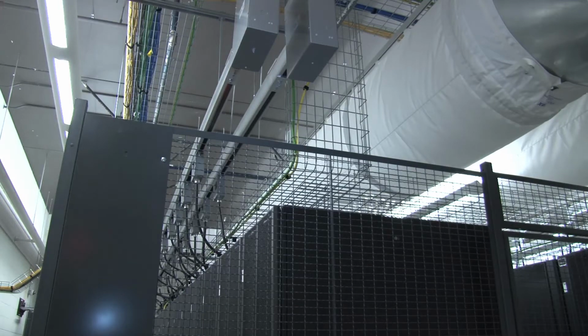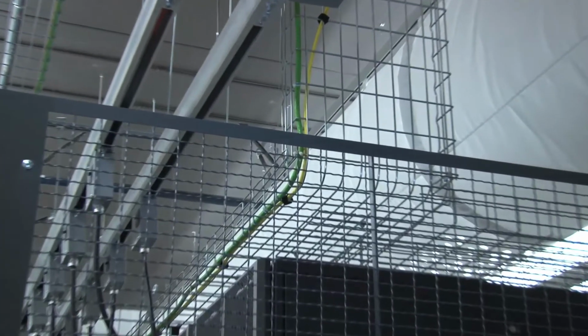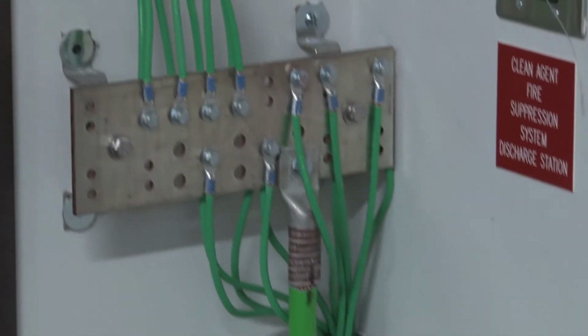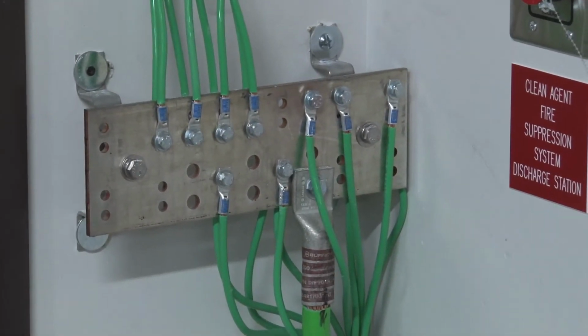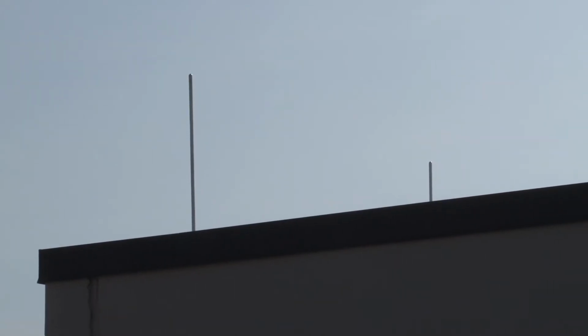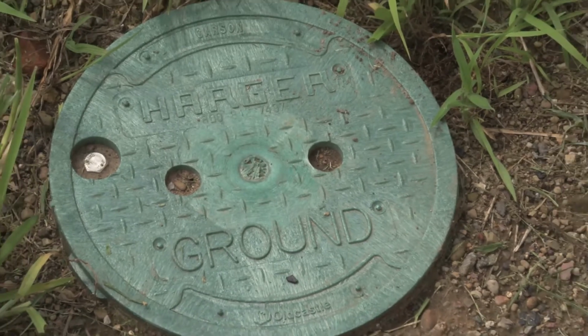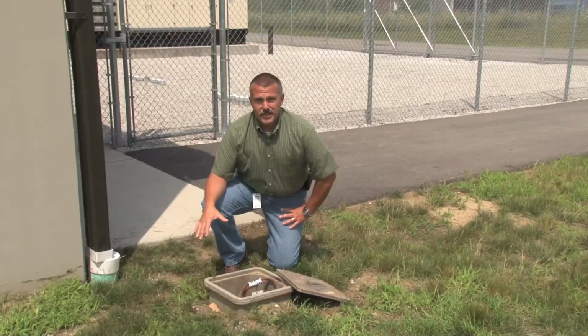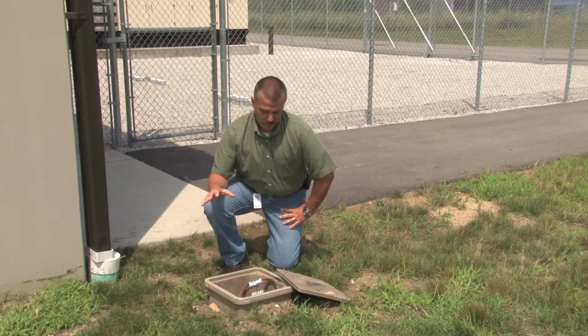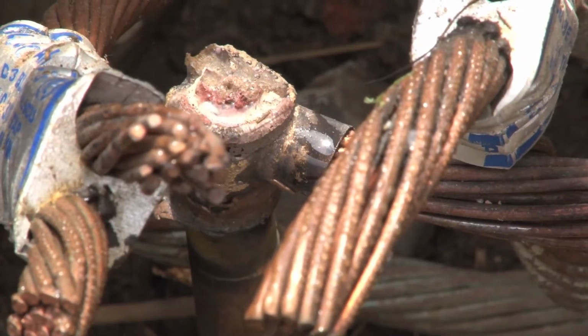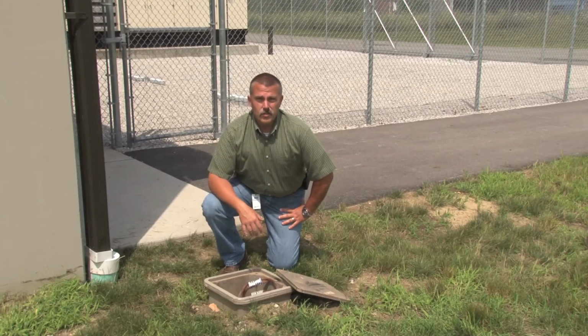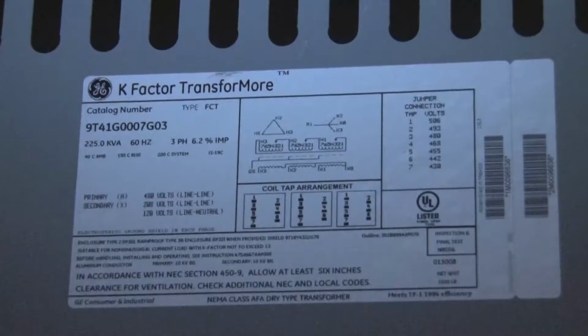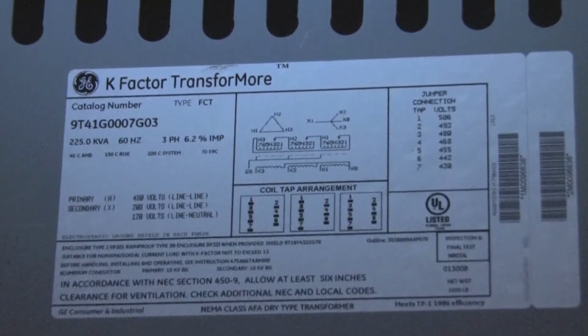And what you'll see in our data centers is a ground wire for the racks to tap into, and then a ground bus for the equipment to tie into, and then a transfer of the outside building protection and those 2 buses into a single common potential or the main ground. We have both a horizontal and a vertical grounding component here, with the ground rod being driven into the ground, minimum of 10 feet, and the horizontal aspects of the ground's going around the perimeter of the building itself. The Involta data centers have transient voltage surge suppression in 2 ways, a system specifically designed for that, and then we also want to isolate harmonics, so we have some isolation transformers associated with our load.